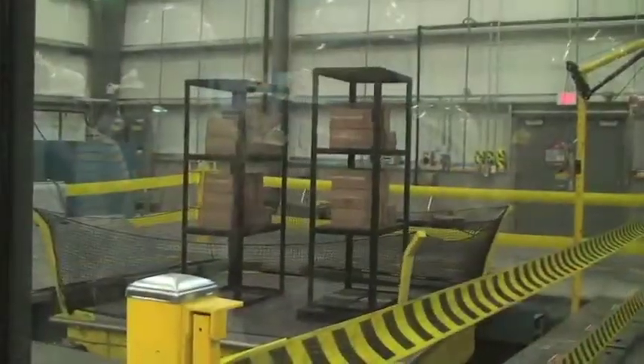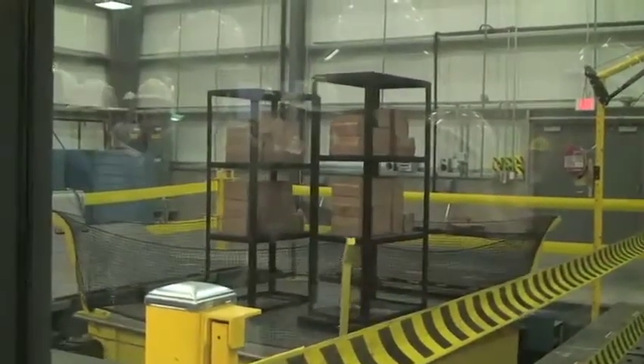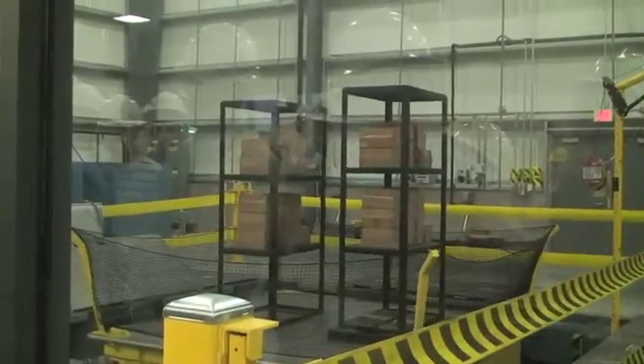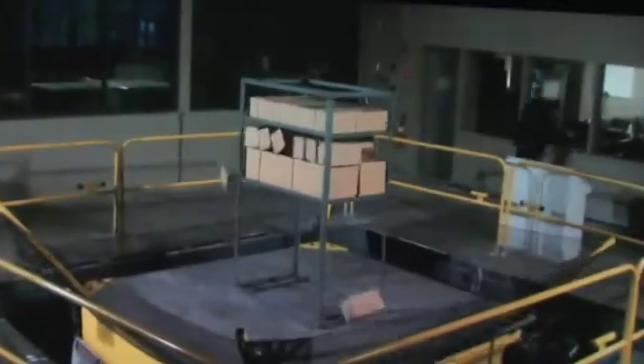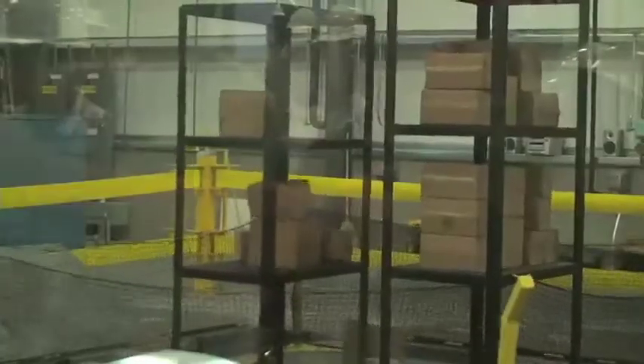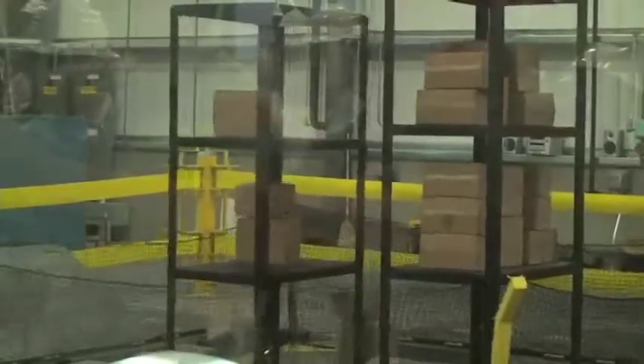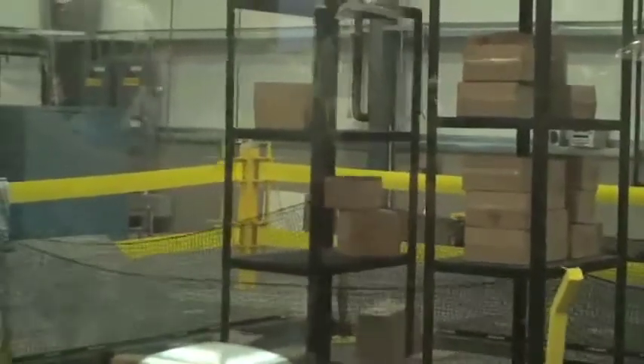The rack on the left is bolted directly to the base of the earthquake shake table. The one on the right has base isolation — the base isolator is bolted, but the rack is almost free-floating on roller bearings. You'll see what happens to the product on those shelves during the earthquake. The base isolated shelving is barely moving, while the boxes on the left are all moving at the same speed, reaching their harmonic — doing a little dance. Base isolation does work: the bolted shelf still stood and is usable again, but whatever product was stored on it is now broken.